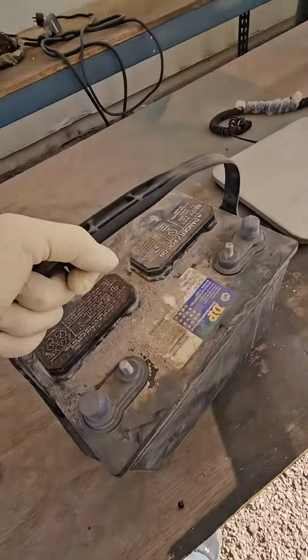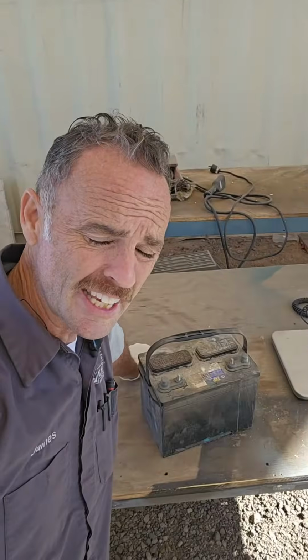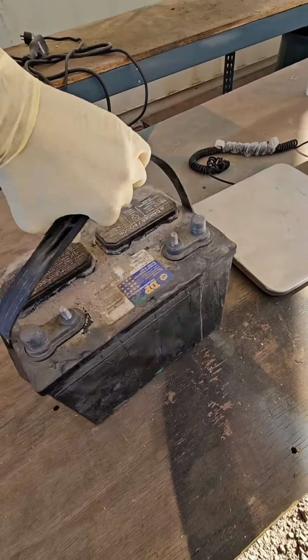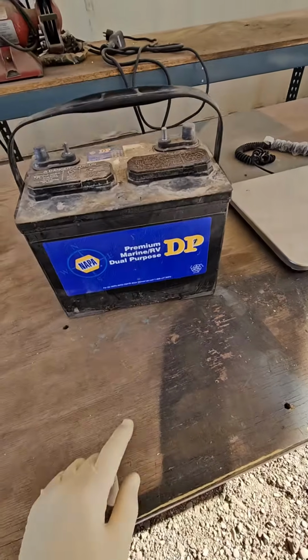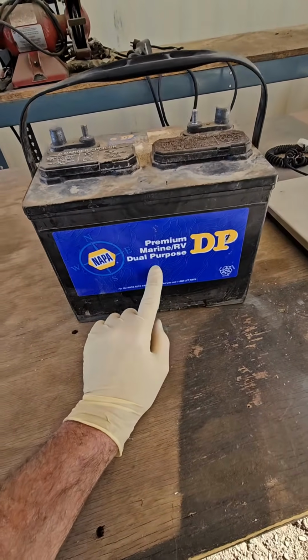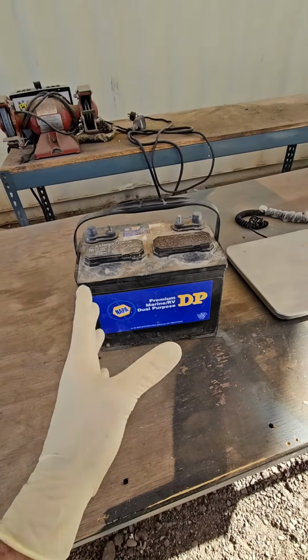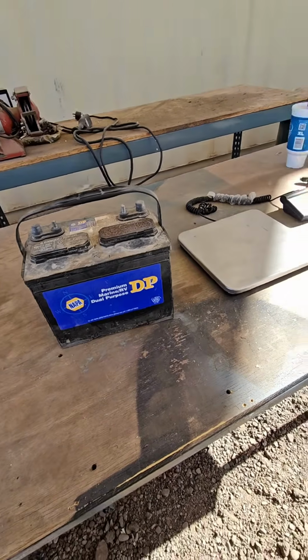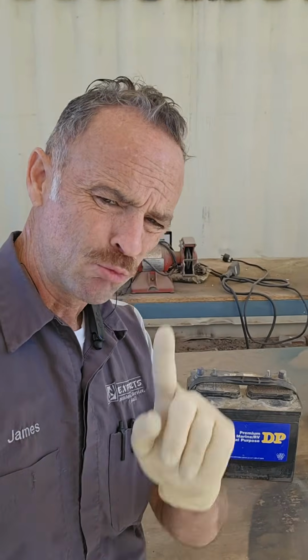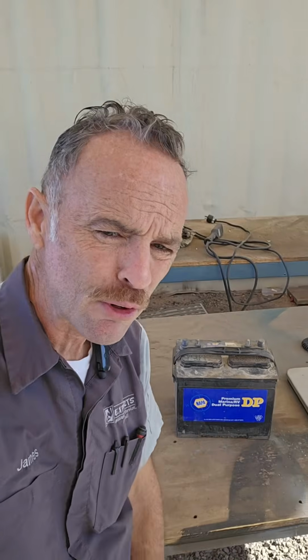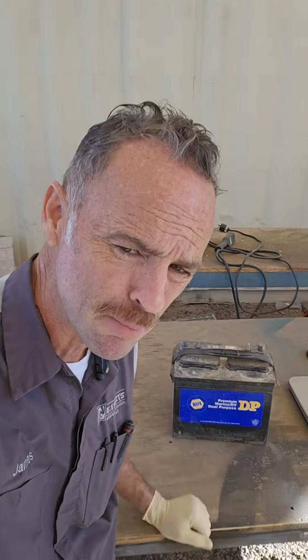It's really a no-brainer at this point, because not only are these lead acid batteries extremely heavy and requiring a lot of care and maintenance, and like to get acid all over the place, a simple Group 24 lead acid deep cycle marine battery only has about 70 amp hours of capacity, and that's total with reserve. You really should only be using about 35 or 40 amp hours of capacity before you start damaging it over time.